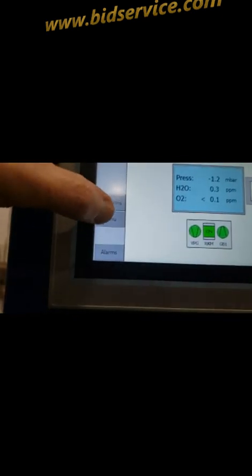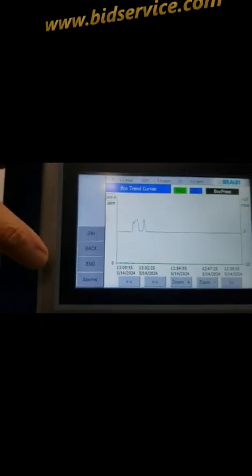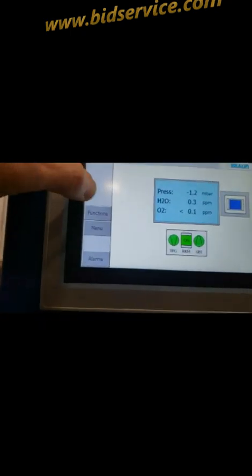Okay, we're going to look at functions here. Well, we went through that already. Additional functions, we looked at that. Let's look at menu. From here, you can go ahead and set your box parameters, your box trend curves. It's not functional, no freezer attached. Service here. When you clean your O2 sensor, you can hit the reset on that. I'll just leave that as is. I cleaned it 5 hours ago.